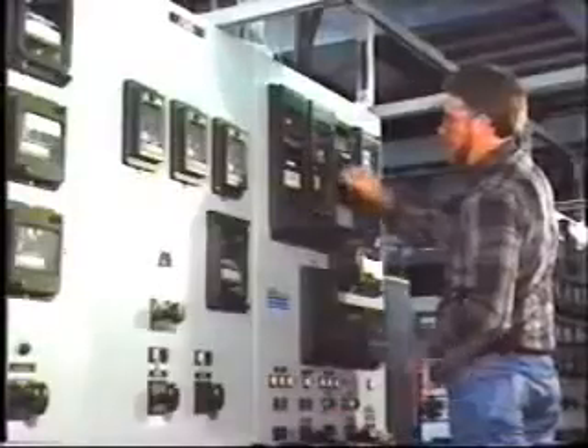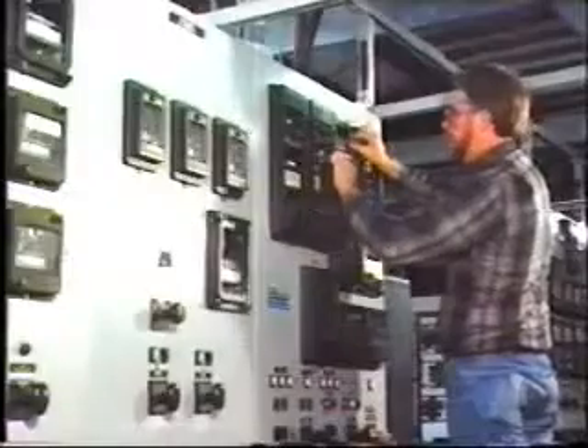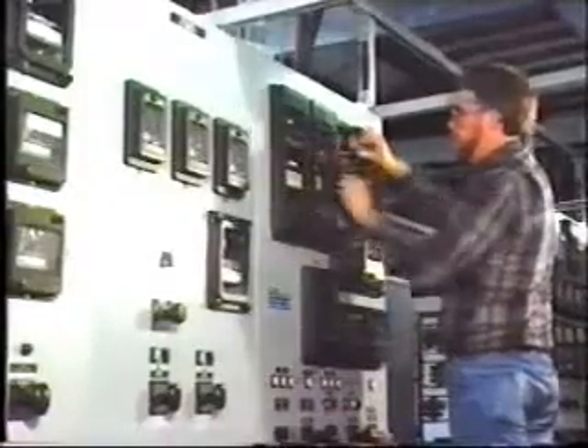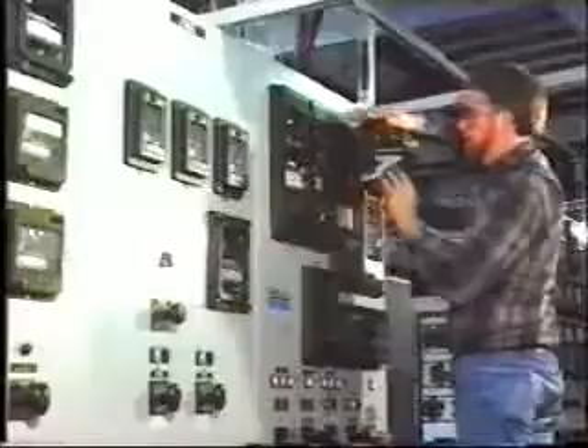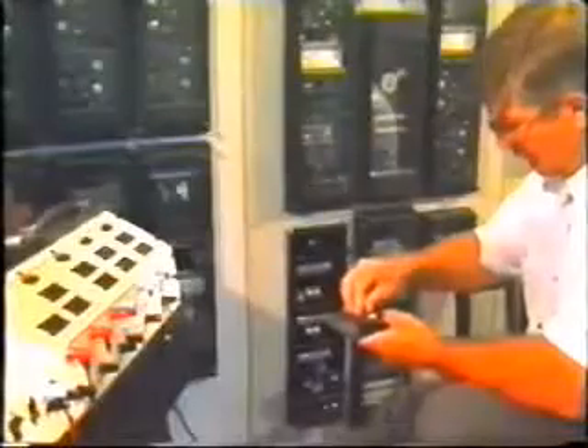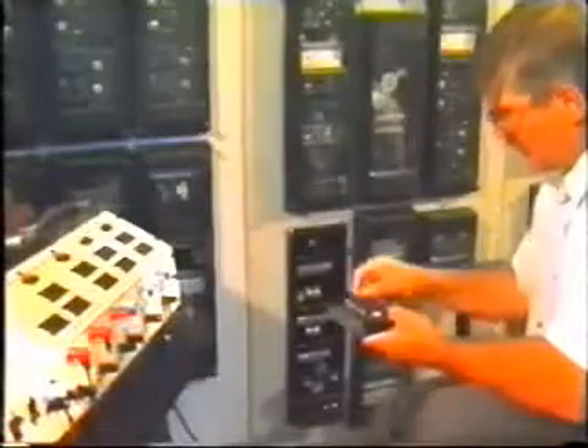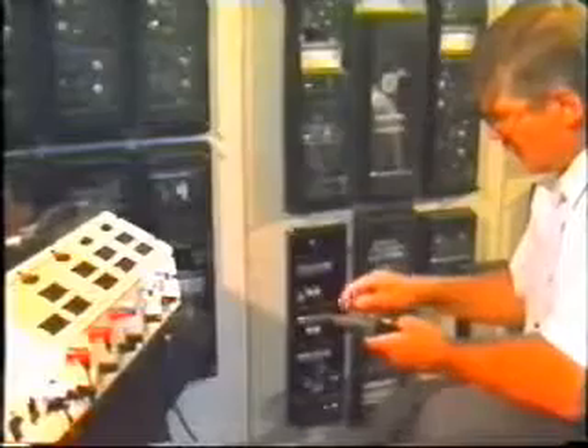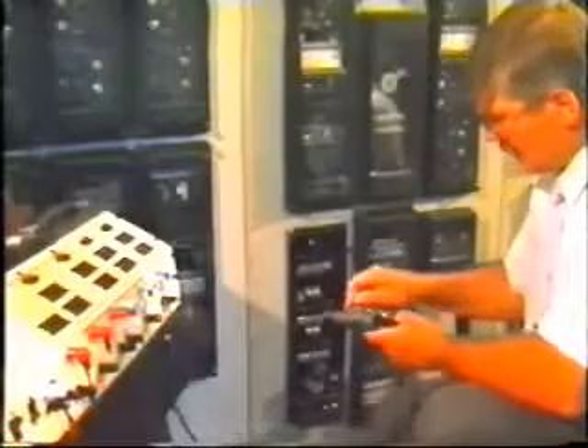When testing relays, we would always prefer to de-energize the equipment and, if possible, remove the relay from its casing. However, we know that this is not always possible. In this situation, make the test block connections, such as external shorts and open potential circuits, before inserting the test block into the relay case.